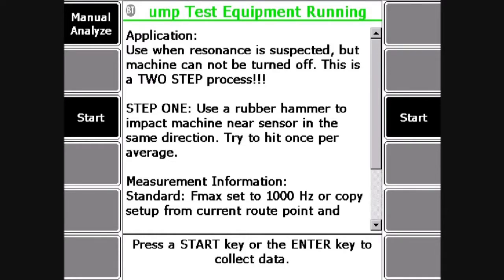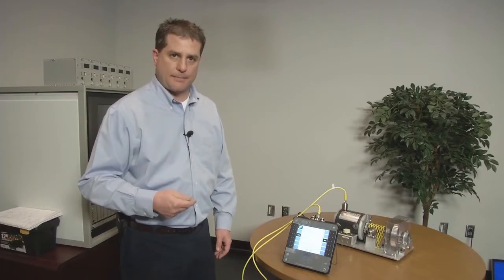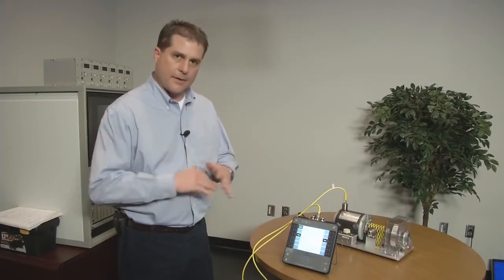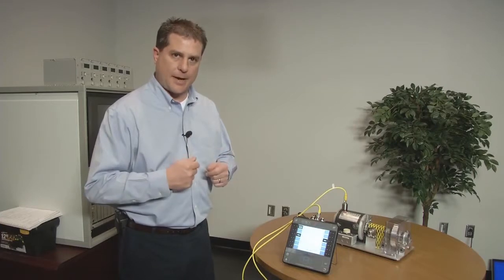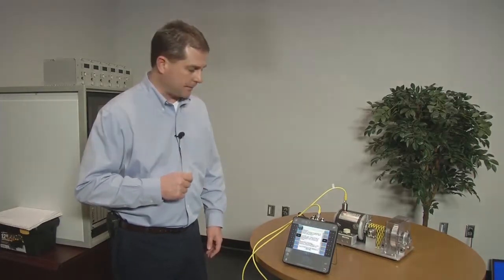It's saying you're going to impact this machine once per average and record the vibration levels. Then for the second step, you're going to stop impacting the machine and record the vibration levels. What it will do is subtract the running vibration of the machine, and what you're left with is the impact. That's the negative averaging. That impact should excite the natural frequency of the machine and show up as the resonant frequency.